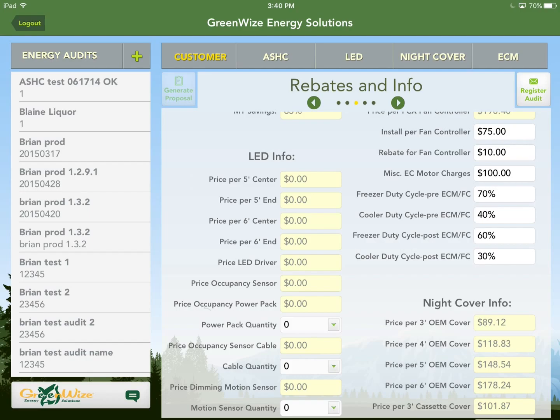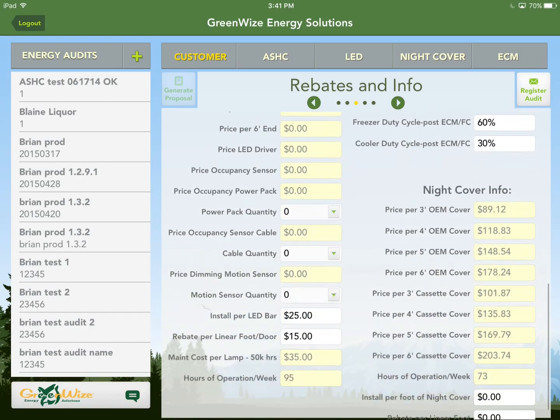The four duty cycle fields only need to be changed when installing equipment in a year-round high-humidity area such as Hawaii or Southern Florida. If your area only has seasonal high humidity, don't worry about it. If you are in a year-round high-humidity situation, contact us and we'll help determine the best percentages to use. Otherwise, skip past those.